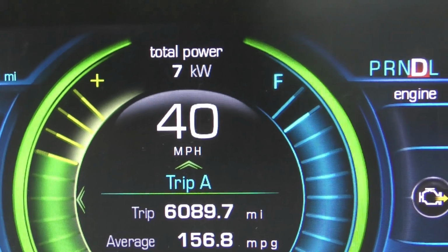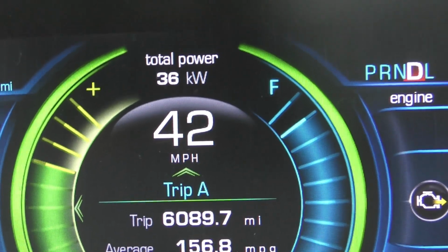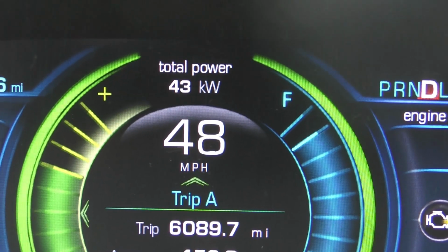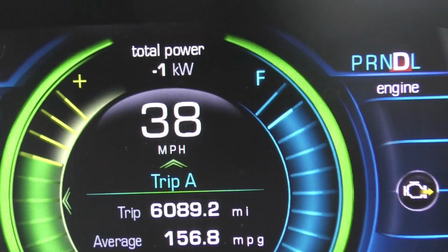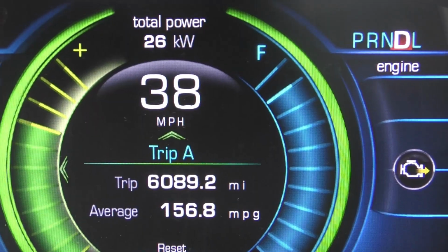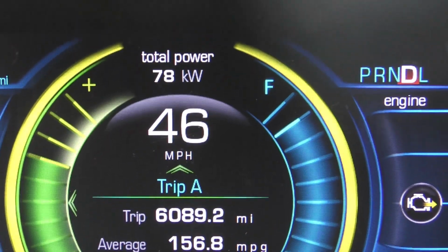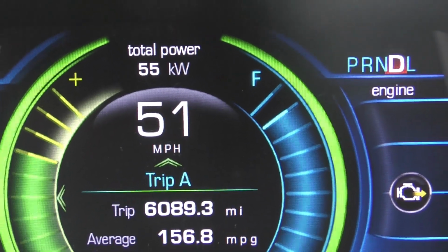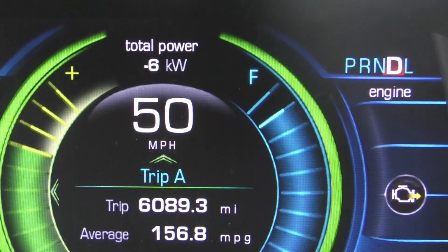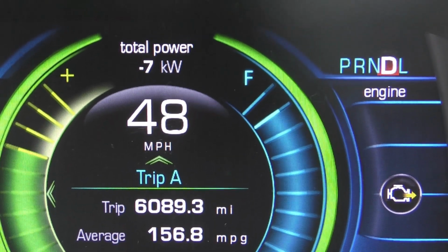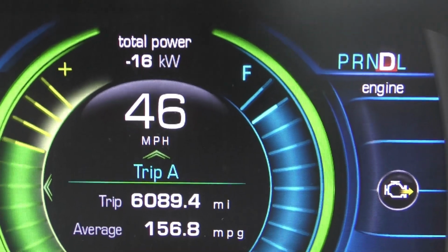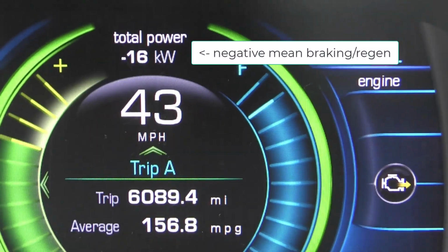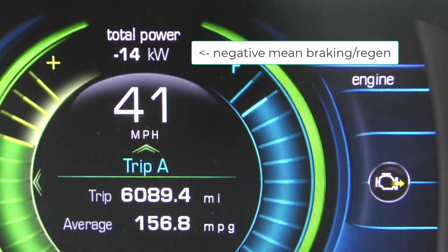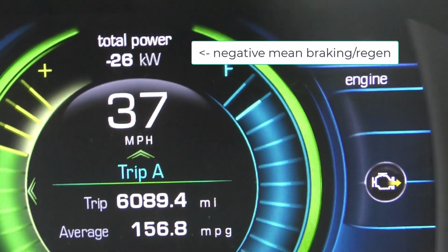With 350 volts, I can push 35,000 watts, or 35 kilowatts, to the motor using only 100 amps, because 35,000 divided by 350 is 100 amps. If my system voltage were half that, like in my EV here, I'd need 200 amps from the batteries to achieve the same acceleration.